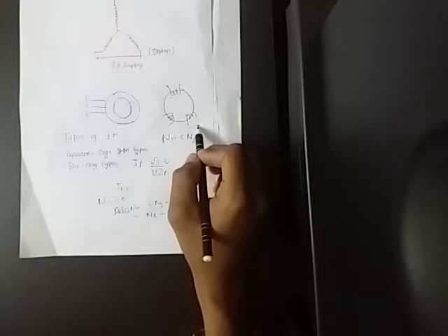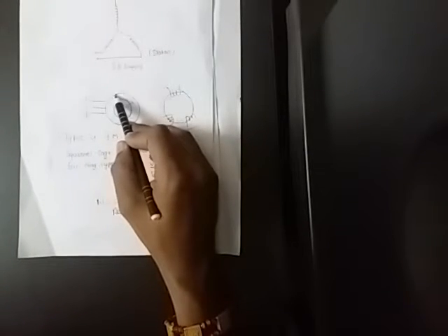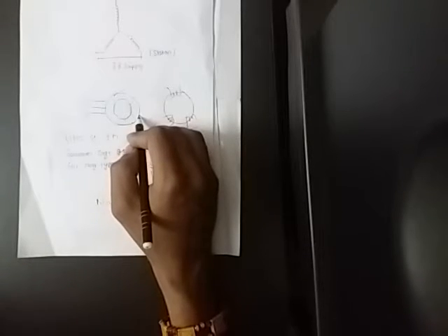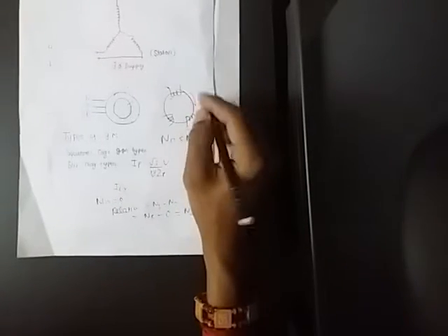A stator consists of three phase winding, as shown in this figure. The three phase windings are placed in slots laminated in the stator, 120 degrees apart. The stator core supports the windings. The windings are made from coils, and each single phase winding is insulated from the others and displaced in space by 120 electrical degrees, as shown in this figure.